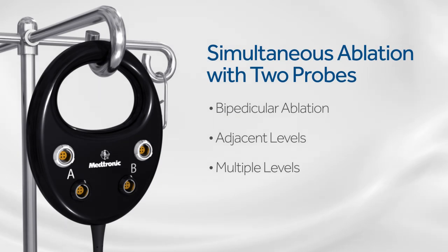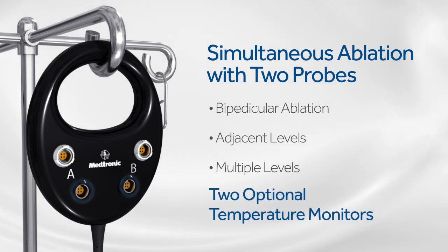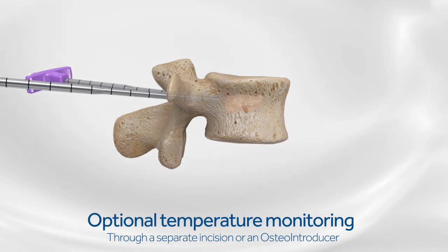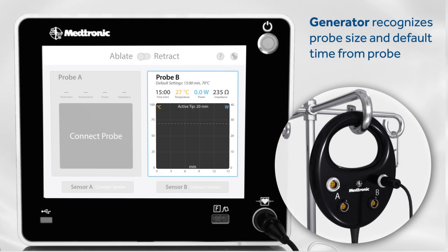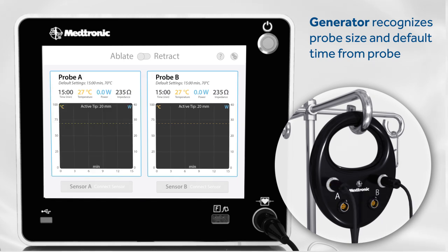of the ablation zone. The connector hub provides 2 channels for probes and 2 channels for additional thermocouples. For additional temperature monitoring, place the independent thermocouples through separate incision sites and near the area to be monitored. Connect the ablation probe to the OsteoCool connector hub. The screen will indicate probe detection and when it is ready for use.